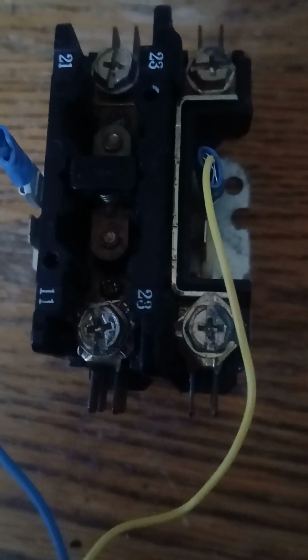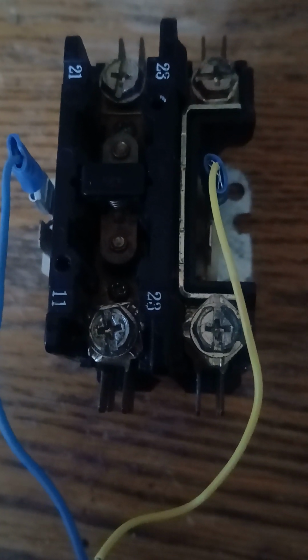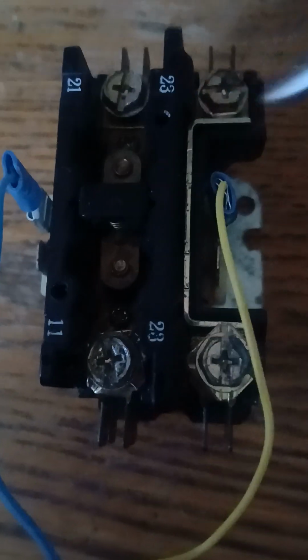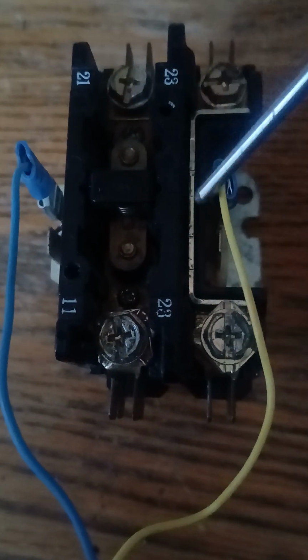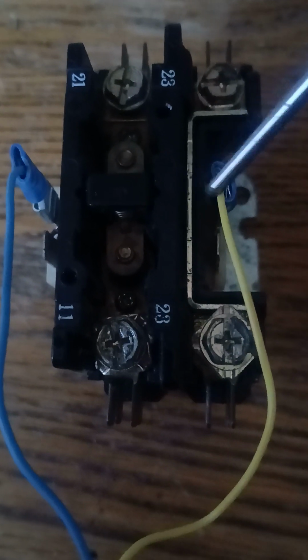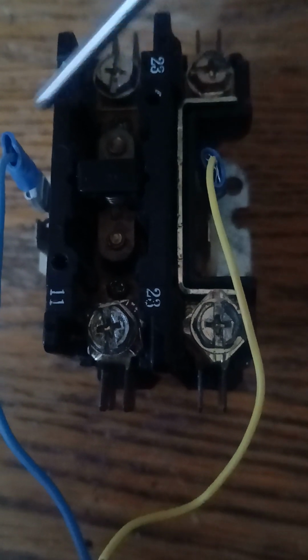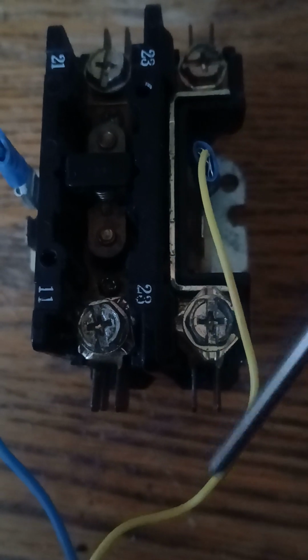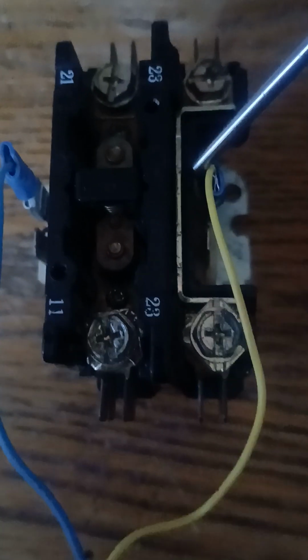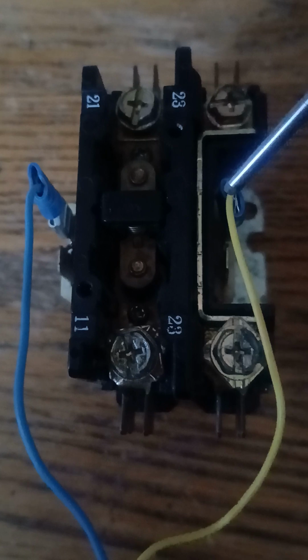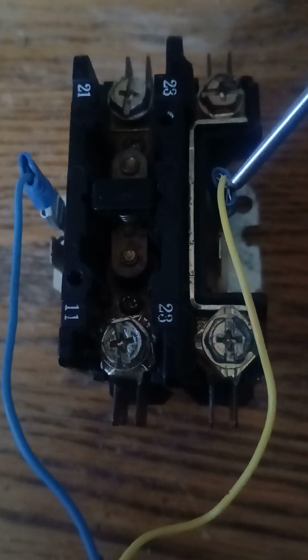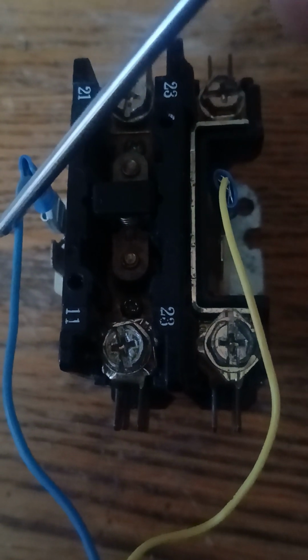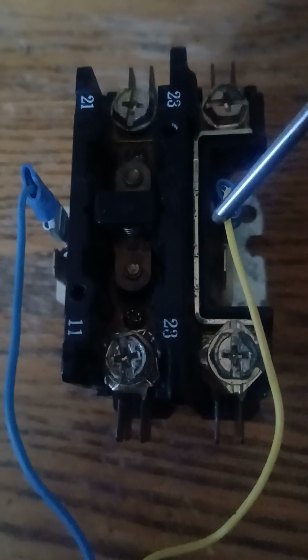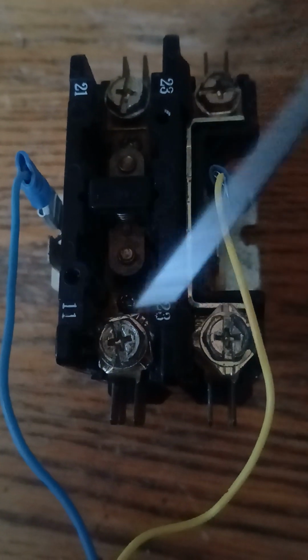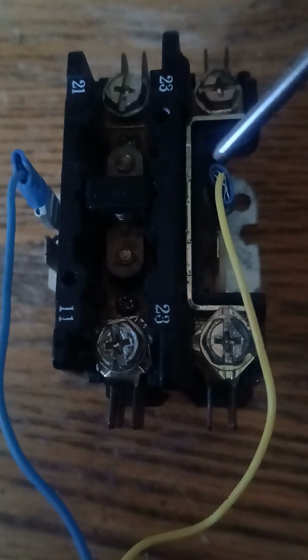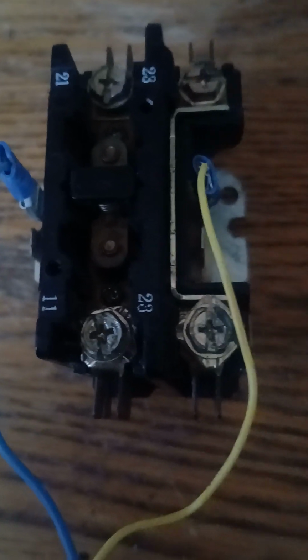HVAC contactor. Question: the low voltage side of the contactor, to power the 24 volts up, which would be this side and this side. Now, one could use the yellow. Sometimes there may be a wire off of here, and then one would pigtail it on down the line. This is fine too. But say if one used the yellow wire and then the blue wire, the common wire, this would be the incoming voltage. This would be the return voltage. Perhaps, I'm not certain on that, but you can look it up.